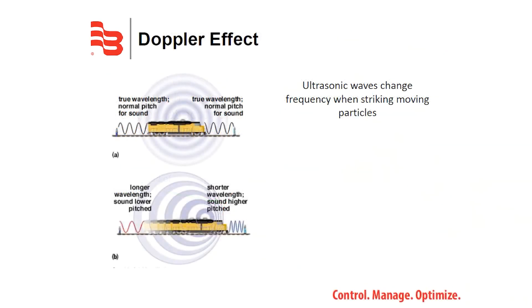With Doppler ultrasonic technology, two transducers are used as well. Unlike transit time, Doppler ultrasonic technology requires the presence of solids or aeration in the liquid. Two transducers are used similarly to transit time; however, one transducer acts as a sender and the other acts as a receiver.